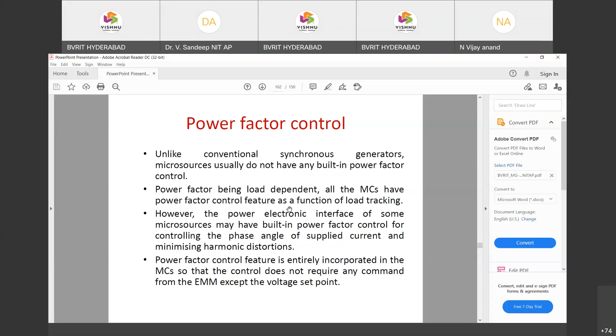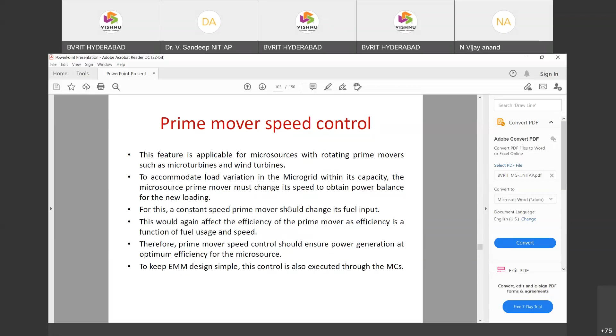Similarly, another control required is prime mover speed control, depending on the generators, particularly in wind energy systems, because when you have variable speed, the frequency will also vary. Even with a constant speed prime mover, you need to change the fuel input, and still the frequency operation varies. Particularly for induction generators operating at constant speed slightly above synchronous speed, your frequency will go down. That is why this speed control is also required.